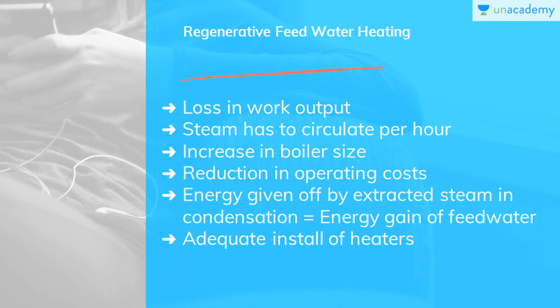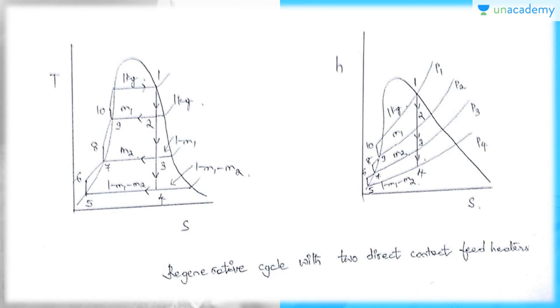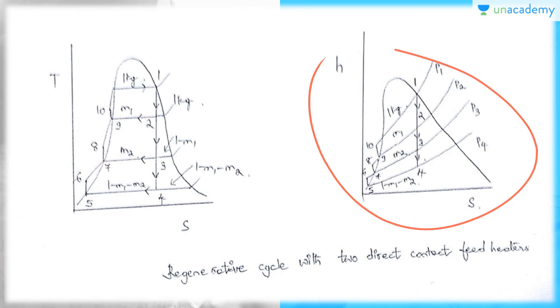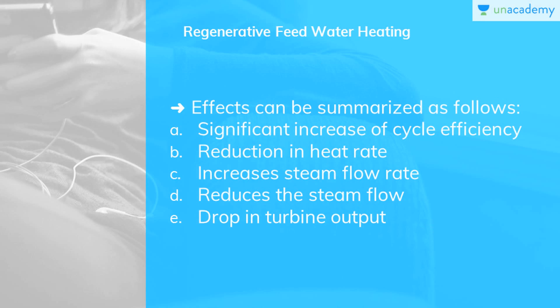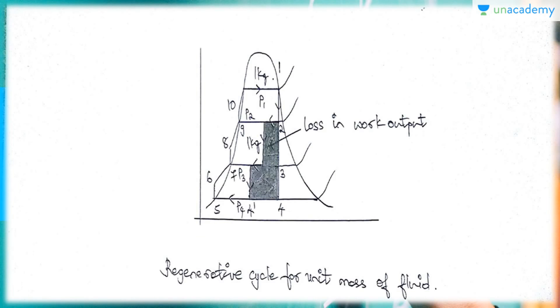The effects of regenerative feed water heating are as follows: it significantly increases the cycle efficiency and reduces the heat rate, that is, the operating cost. It increases the steam flow rate, it reduces the steam flow to the condenser, and if there is no change of boiler output, the turbine output drops. You can see the regenerative cycle T-S diagrams and H-S diagrams with two direct-contact feed heaters. This is the reduction in heat rate, increased steam flow rate, and drop in turbine output. The hatched area shows where the loss in work output happens. This is the regenerative cycle for a unit mass of fluid.